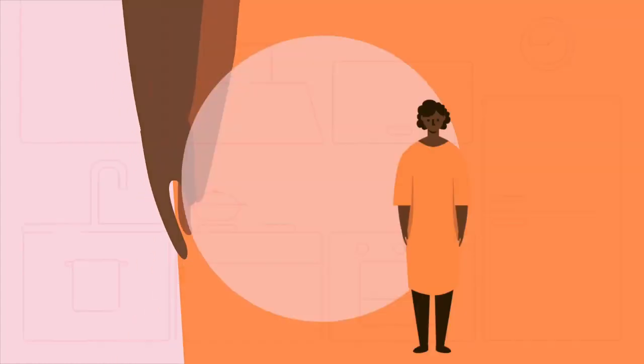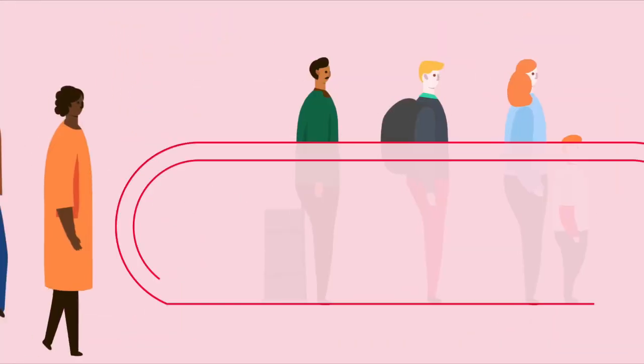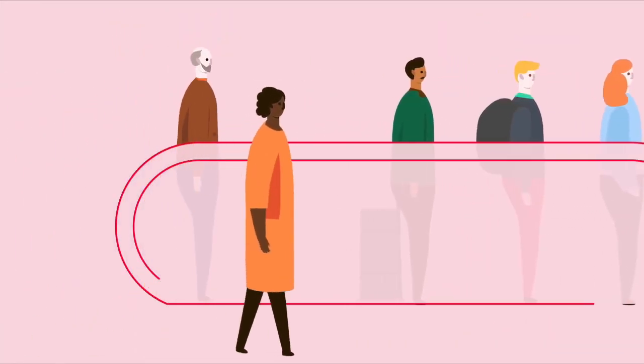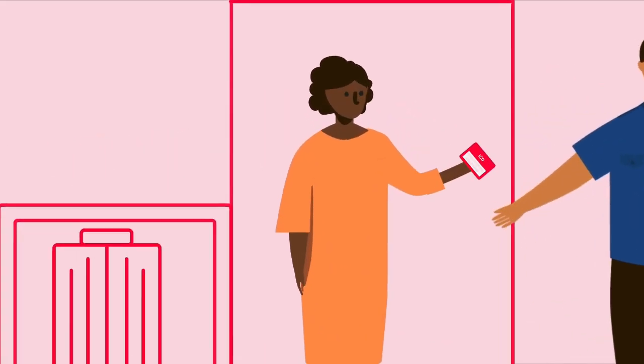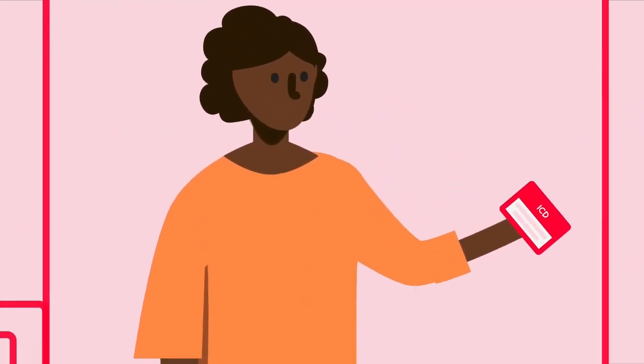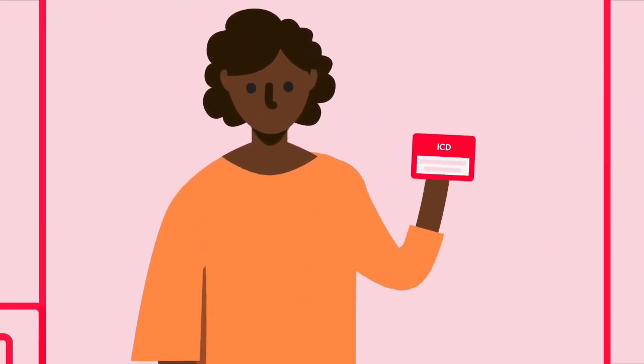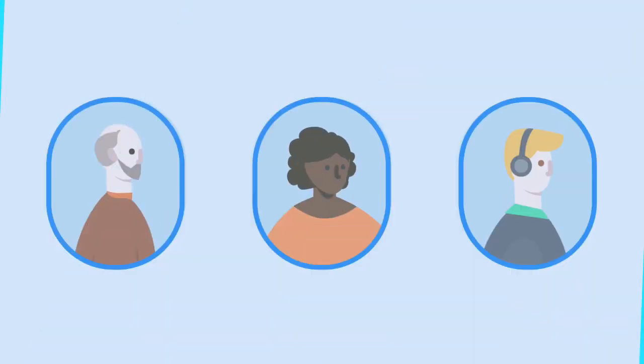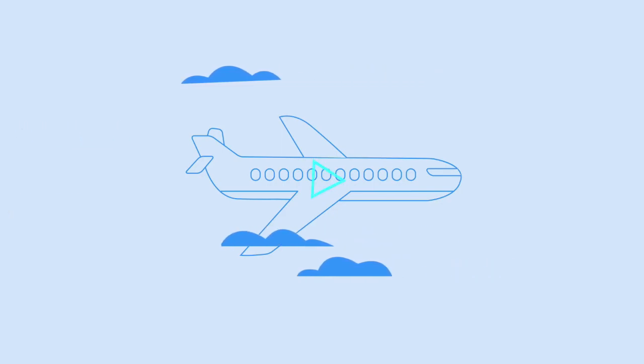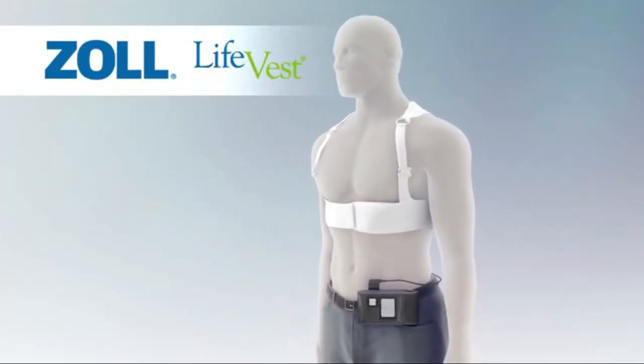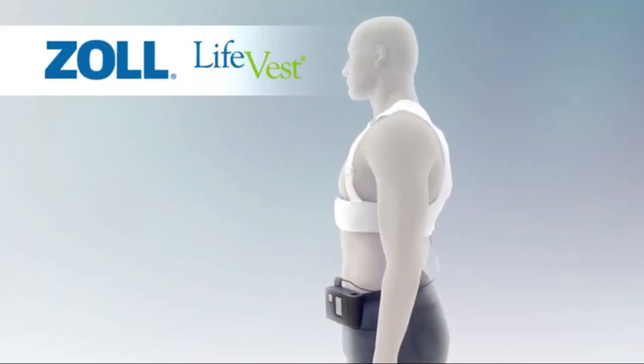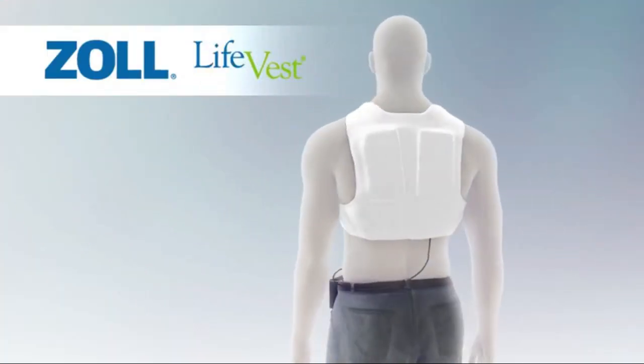Some devices may attempt overdrive pacing prior to synchronized cardioversion. When the life-threatening arrhythmia is ventricular fibrillation, the device is programmed to proceed immediately to an unsynchronized shock.